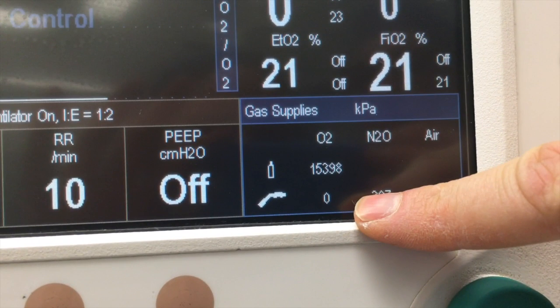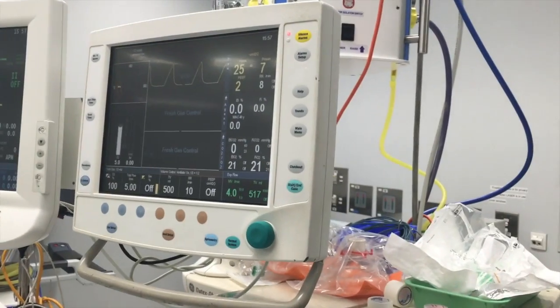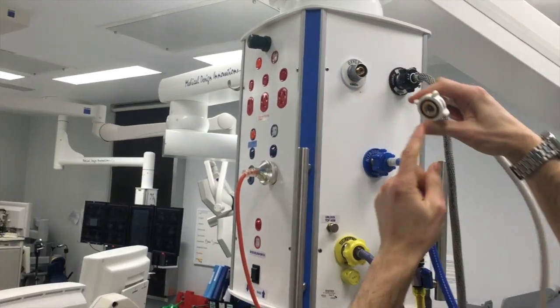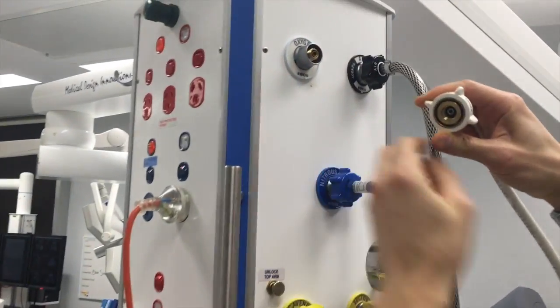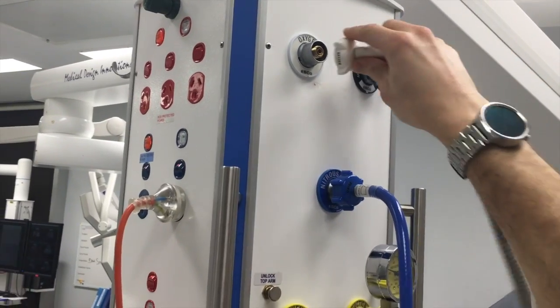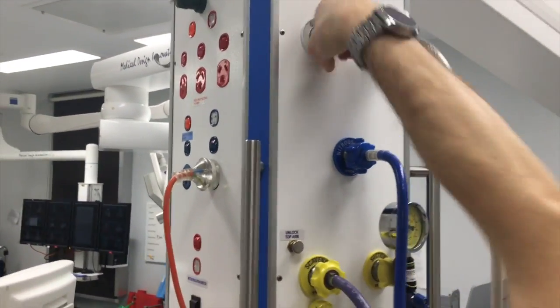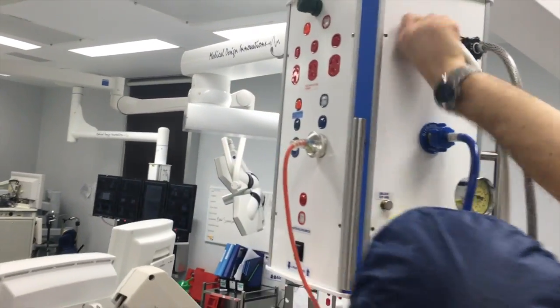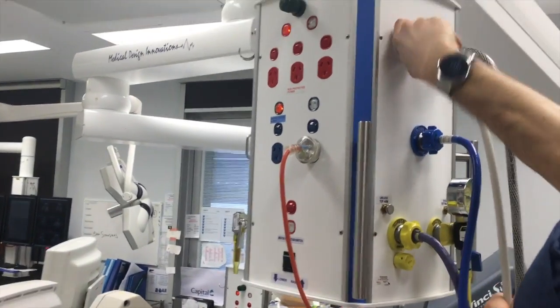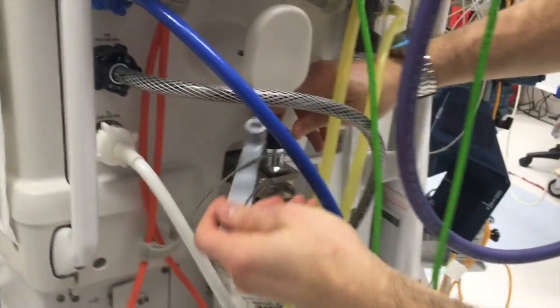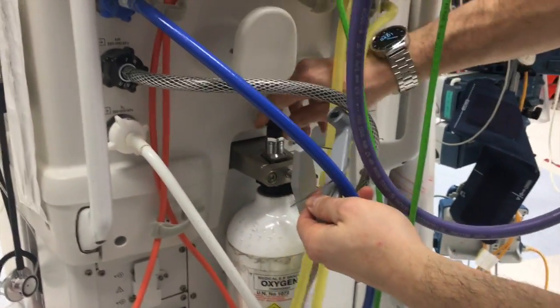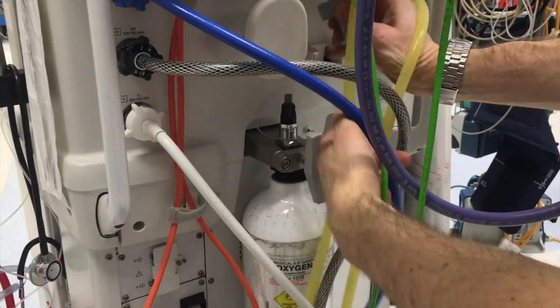Note that the nozzle symbol indicates that wall pressure is still 0. You need to fix this by reconnecting the oxygen supply from the wall. The inside of the connector has a specifically sized metal disc that will only fit onto the oxygen wall supply. This feature, along with the colour coding, ensures that no gases are mixed up. Now you need to ensure that the backup cylinder is firmly turned off so that it doesn't empty out due to any small leaks during the case.